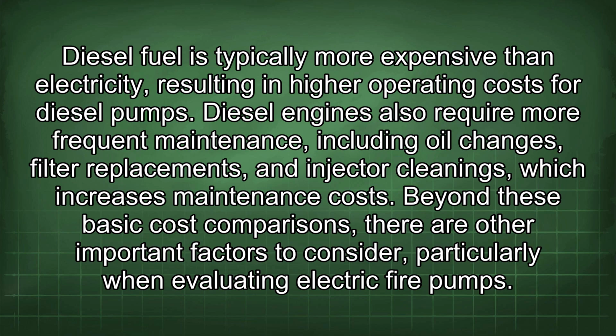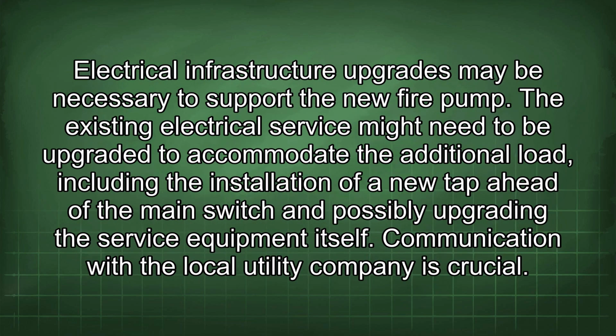Beyond these basic cost comparisons, there are other important factors to consider, particularly when evaluating electric fire pumps. Electrical infrastructure upgrades may be necessary to support the new fire pump. The existing electrical service might need to be upgraded to accommodate the additional load, including the installation of a new tap ahead of the main switch and possibly upgrading the service equipment itself.